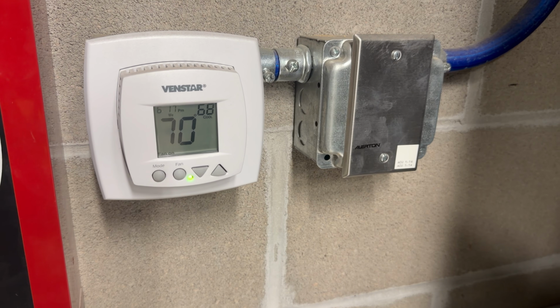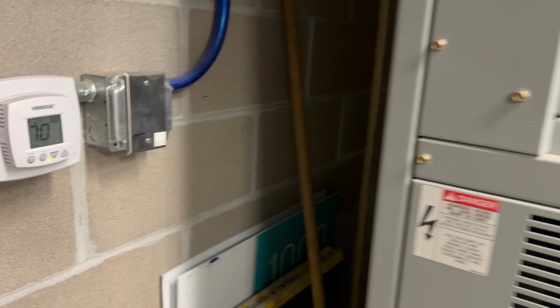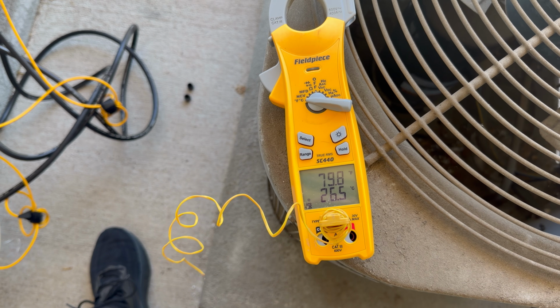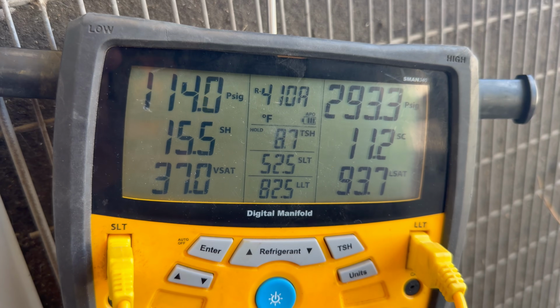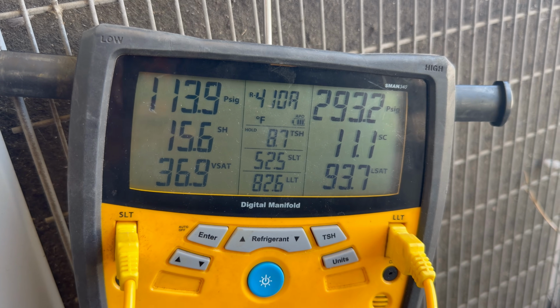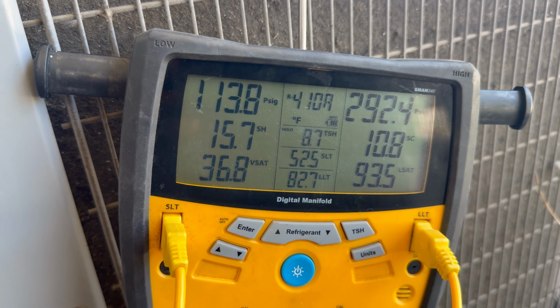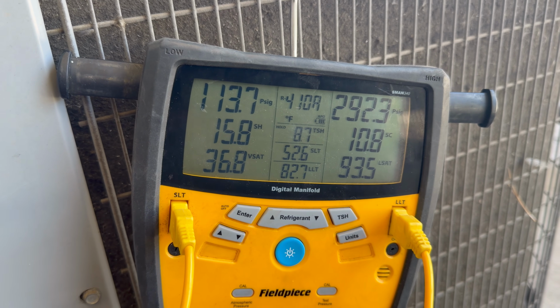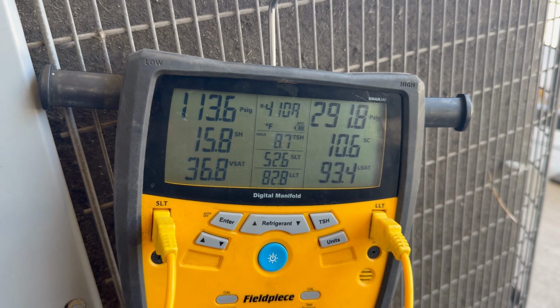So what I'm gonna do today is turn this unit on. I'm gonna check pressures, check compressor amps, and then we're gonna go ahead and clean the unit and see how much it affected it. Indoor load 70 degrees in this electrical room. Outdoor load is 80 degrees. And those are the readings we're looking at. 293 head pressure, 11 subcool, 114 suction, 15.6 superheat. Just off these readings alone, this does not look that bad.